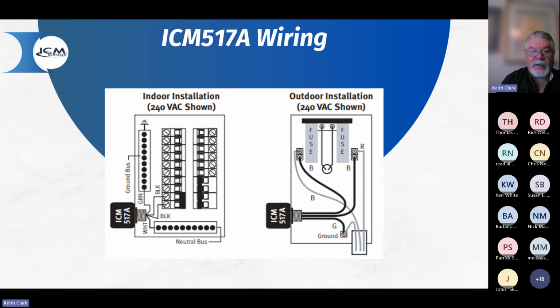And we have those as well, the ICM518, and those are 200,000 amps. So they're twice the protection that the 517 is even. I had to make a correction on that. Okay, I'm sorry, they are 100,000 as well. Where you get more protection with the 518 is the number of hits that it can take. The nominal discharge current on the 518 is 20,000. It's 20 kA nominal discharge current, rather than 5 kA of the 517A. But the total protection for a single hit is the same, 100,000 amps. Sorry about that. But again, the 518 is a type 1 device, so it can be used as whole home, whole panel. And the 517 is designed for a single device or a single breaker.